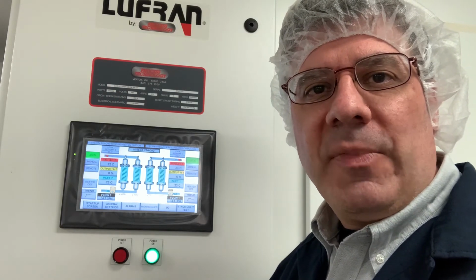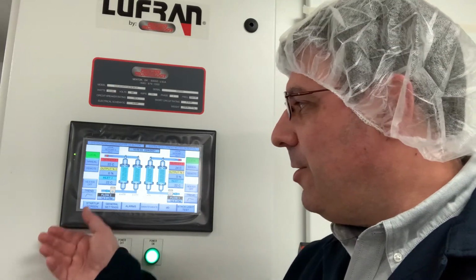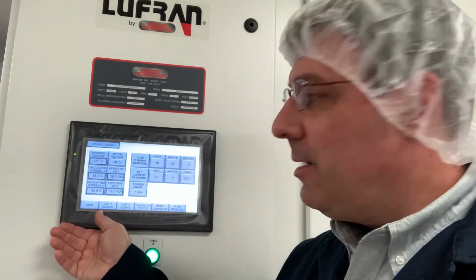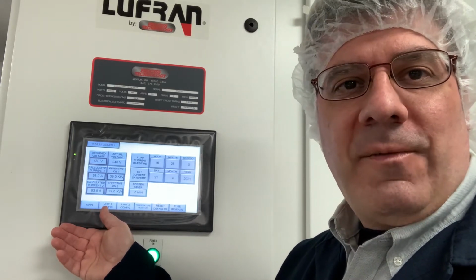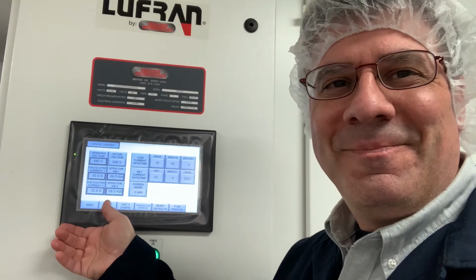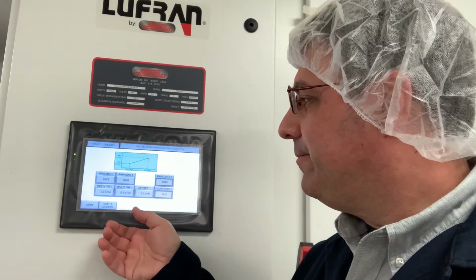So to access the flow calibration procedure, you need to go into the flow calibration menu. To get to the menu, go to your general settings button and then press your unit 1 configuration menu. Here's unit 2. We're only going to do unit 1 today. And then across the bottom, you've got a button for the flow calibration menu. Press that. This is the menu screen.